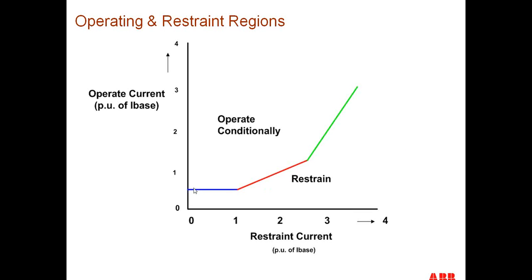So now that we have this relationship, we know that any current that is below this operating curve, the relay will restrain from operating, and any time that the operating current is above this restraint current, you will be in the operate region. Why do we have three different slopes for this operating curve?